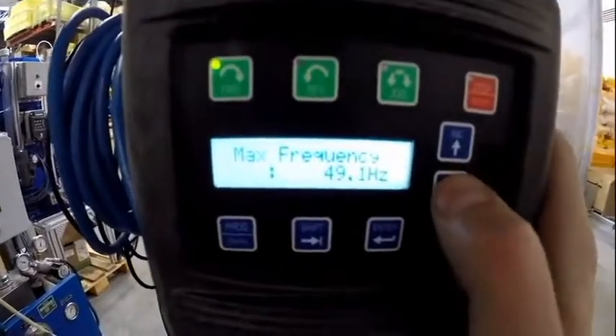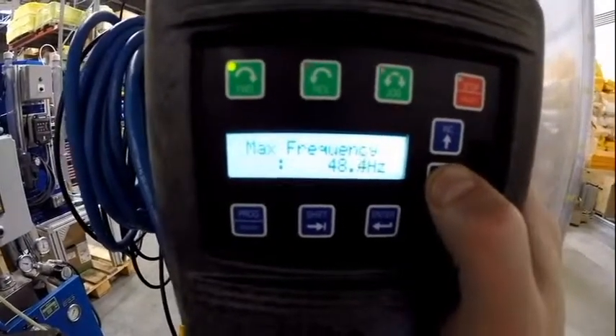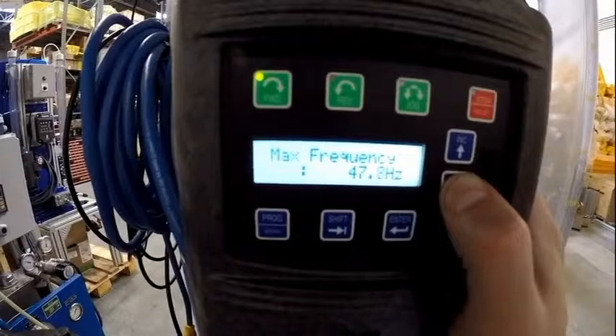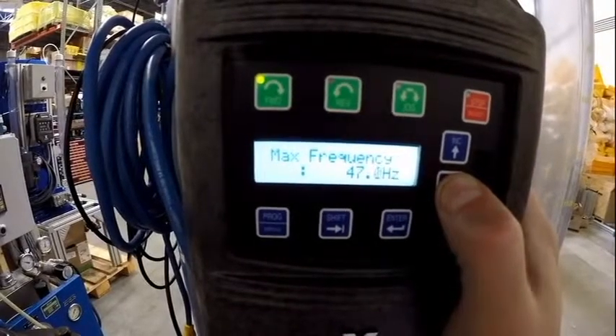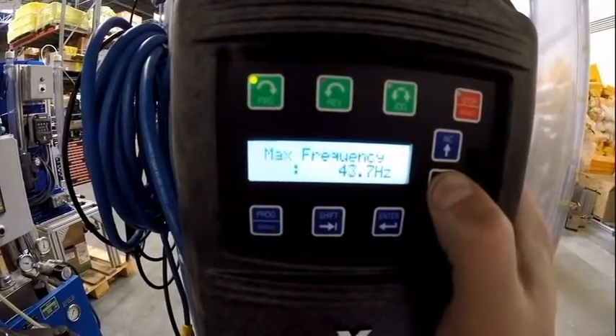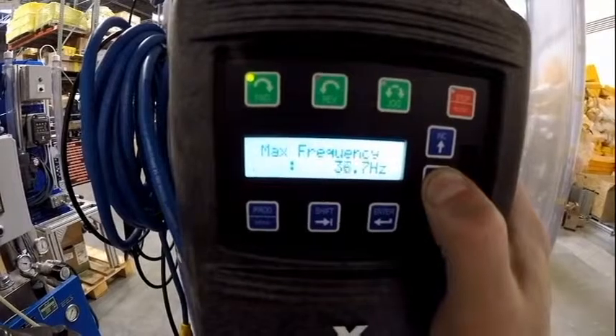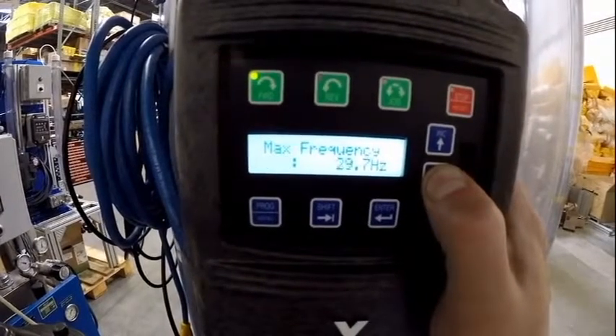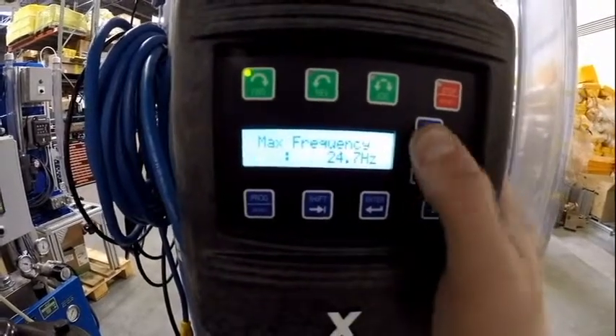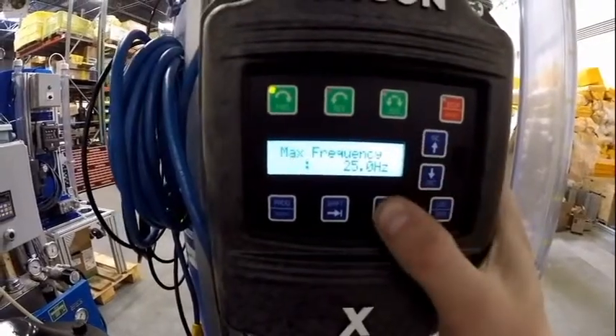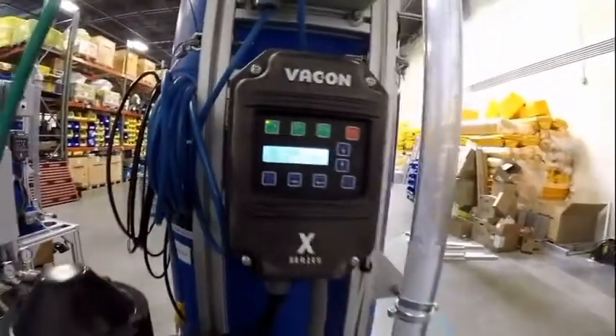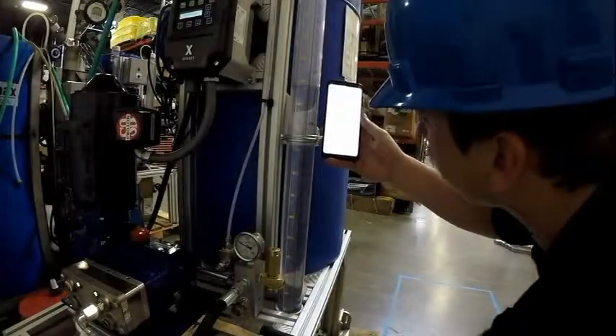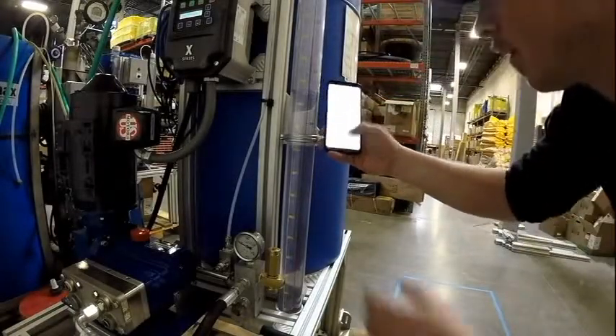Since we're pumping too fast, we need to lower the max frequency hertz. We started at 50. I normally run it down to about half, so we'll go down to right around 25. Then you're going to press enter to store the settings. We will then go back and do the calibration over again. So you're going to turn the valve and push the start button.